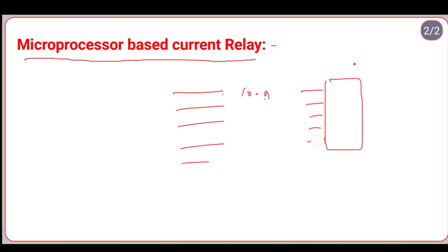If any fault occurs in any circuit, the microprocessor can sense the fault and give the signal to the circuit breaker, or it can inform us also. By the use of the computer, we can know what the fault is, where the fault is, and what type of fault it is. If the fault current in any circuit connected to a CT exceeds the pickup value, the microprocessor sends a tripping signal to the circuit breaker of the faulty circuit.